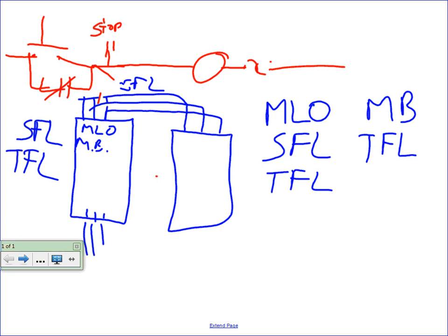And on these panels, you can get up to like a 125 amp max branch breaker in them. It plugs onto the bus. I believe we have main breaker up to 600 amps and main lug up to 800. But we're still limited to the size of breaker we can put in the panel. So on your project, you might have a couple 200 amp breakers on that panel, right?